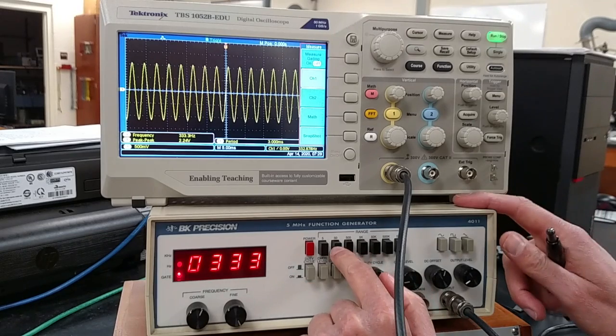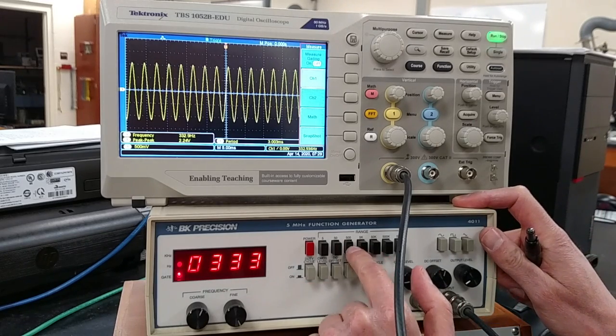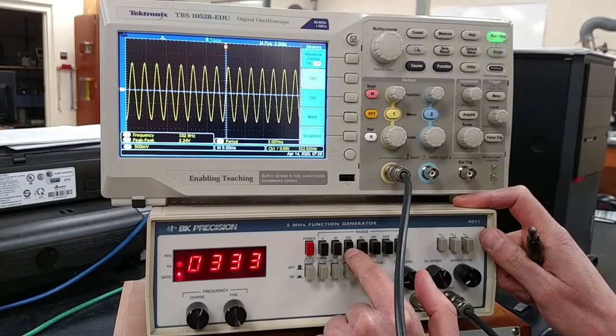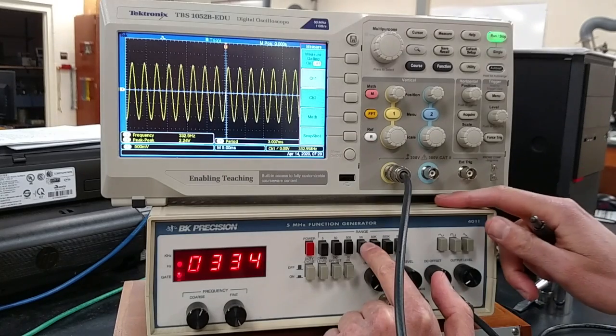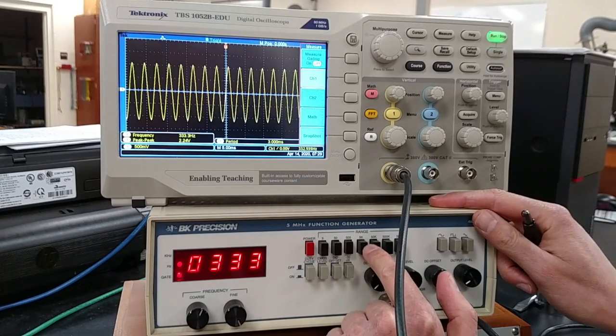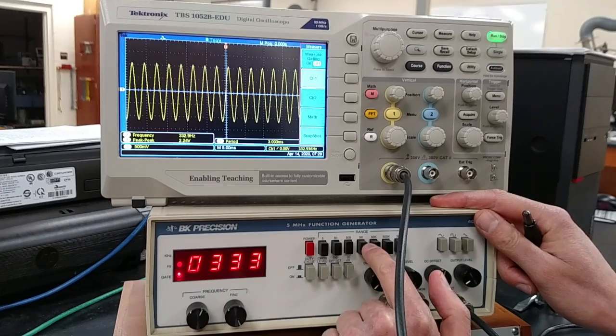Finally we can see what happens when we change the range. For example, we are now at the 500 hertz setting, the frequency is 331 hertz. So if we go to the 5k range that should multiply by 10 the frequency.